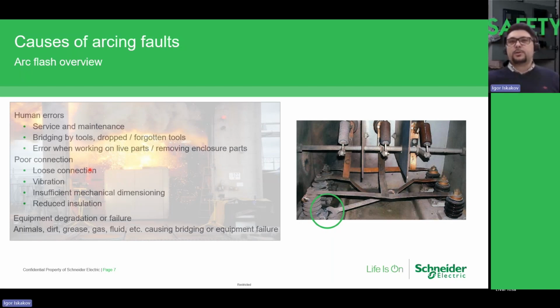Poor connection, of course: cable endings, if they are not connected properly, or they are quite old and the connection is loose from vibration and other causes. This can bring first a small arc fault, and after that, finally, the arc flash. Reduced insulation is the same, it usually brings an arc fault. In production, an arc fault is not a tripping, it's usually an alarm. And after that, when you have an arc fault, it can develop into the arc flash, and it's also the case of arcing faults.